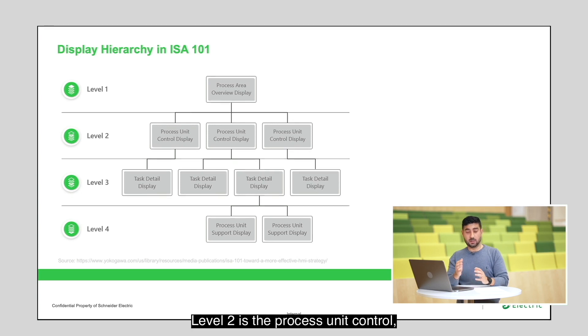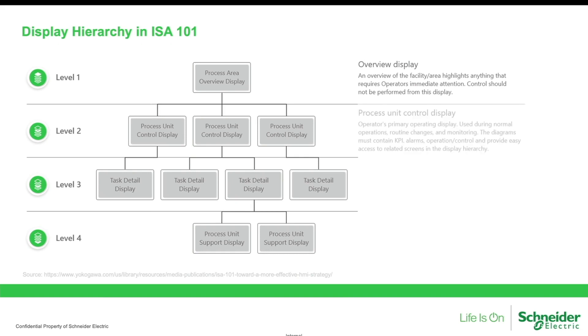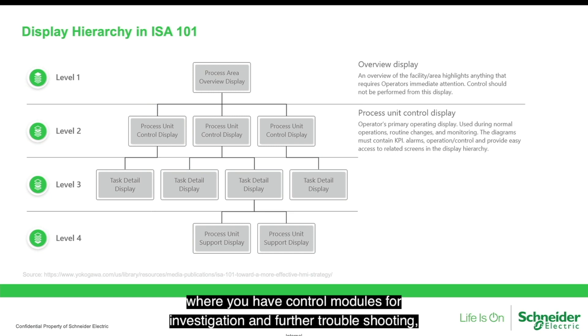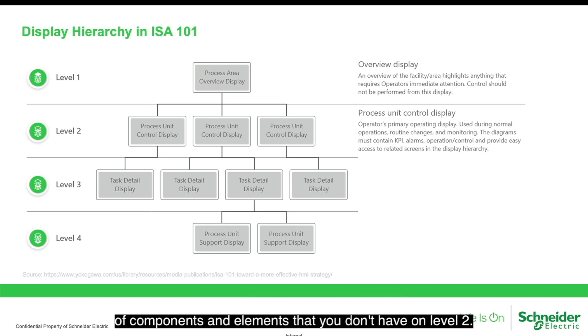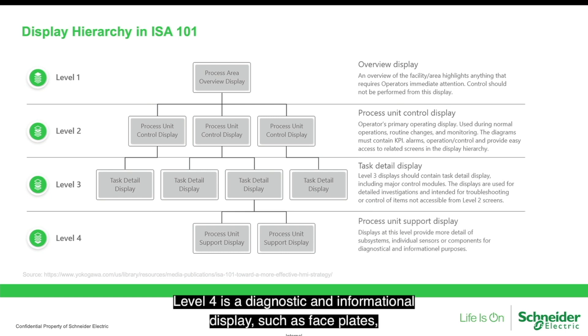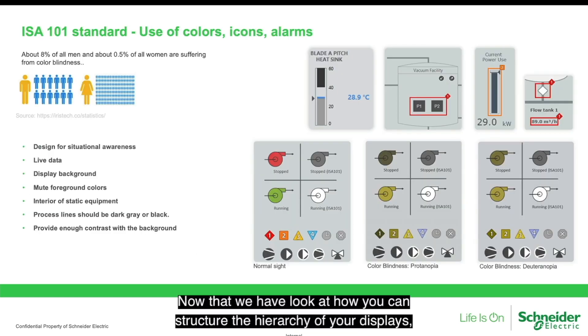Level two is the process unit control, where you display major task control and operation. Level three is a more detailed task display, where you have control modules for investigation and further troubleshooting of components and elements that you don't have on level two. Finally, level four is a diagnostic and informational display, such as face plates, where you provide more details of your components such as pumps and valves from the level three displays.